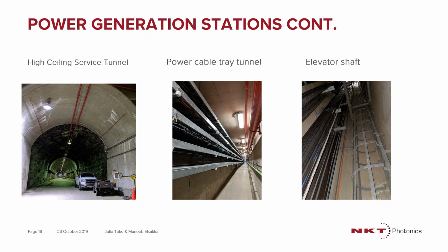So you can set pre-alarm parameters to say if this cable tray is overheating a little bit more because there's more current going through these power cables, then we can set up an alarm or a ventilation system to make sure that the air can be pushed through, and/or deploy some other alternative type of services where somebody can actually reduce the load on the cable. So it enters the world of not just detection, but also prevention.